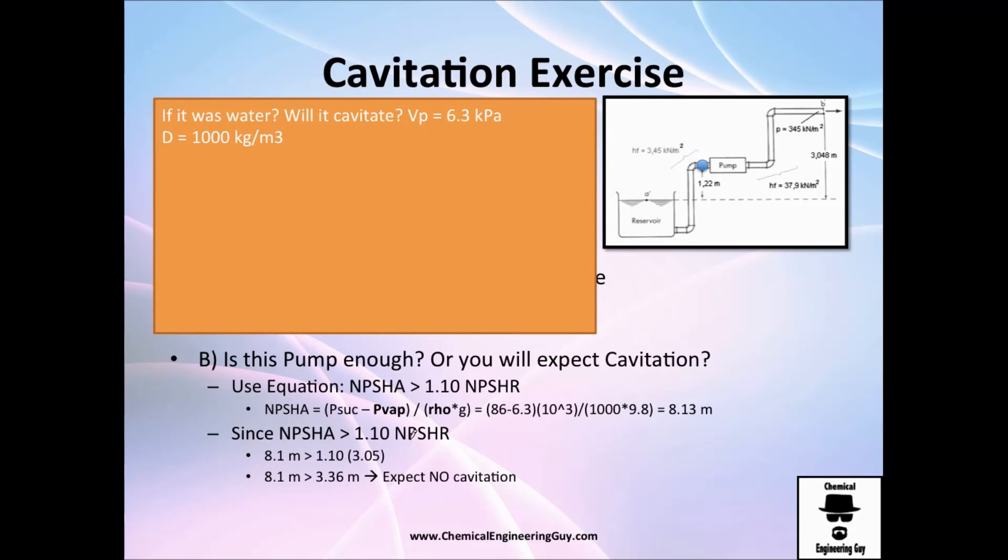Let's do the same exercise for water. Let's suppose we have the vapor pressure right here, 6.3 kilopascals. We got the density. So let's go back and see if this pump is enough. The pressure in the suction line will be the same, 86. The only thing that changes is the vapor pressure and the density of our fluid. Gravity is constant.